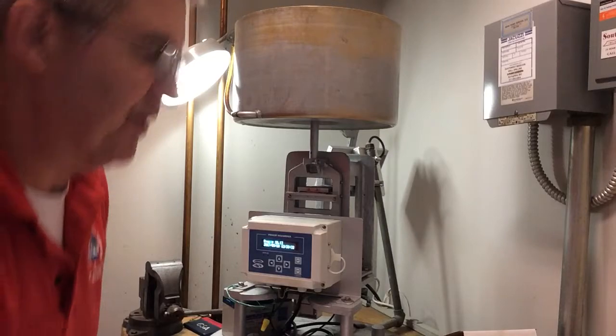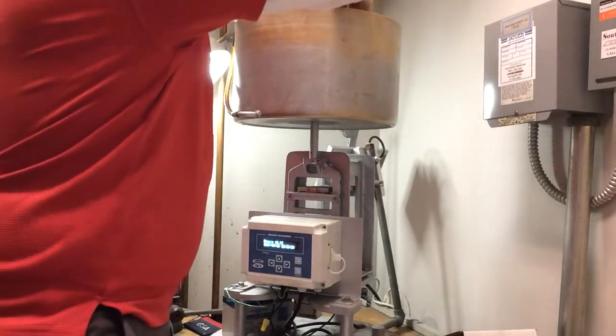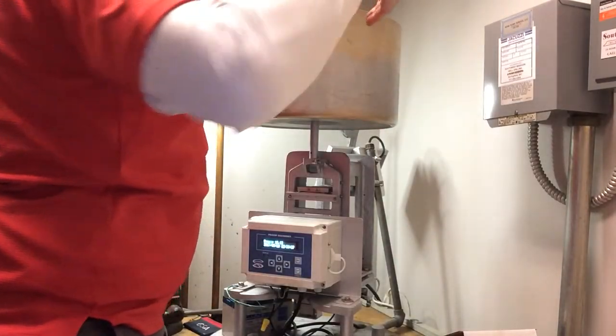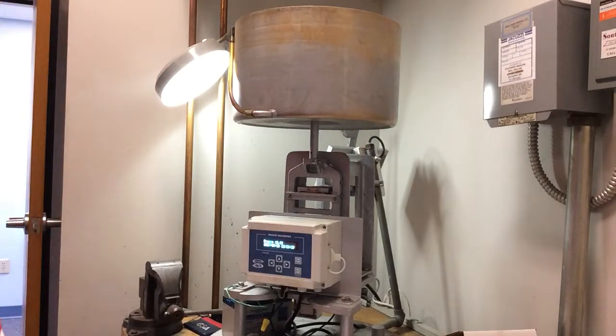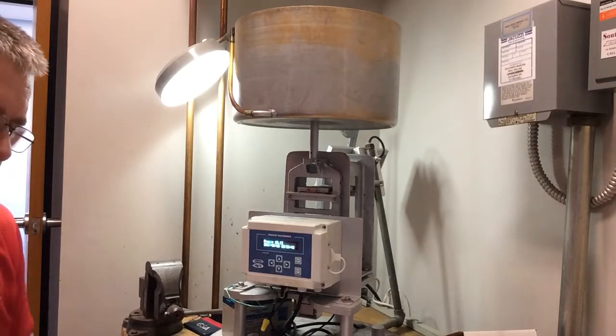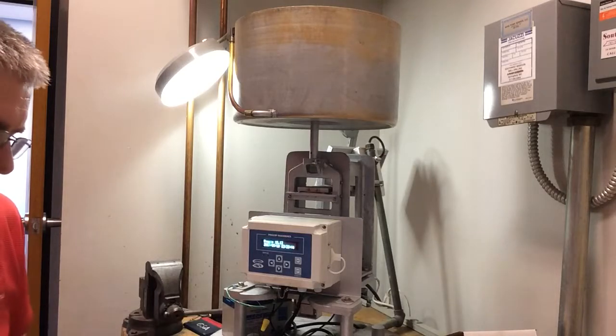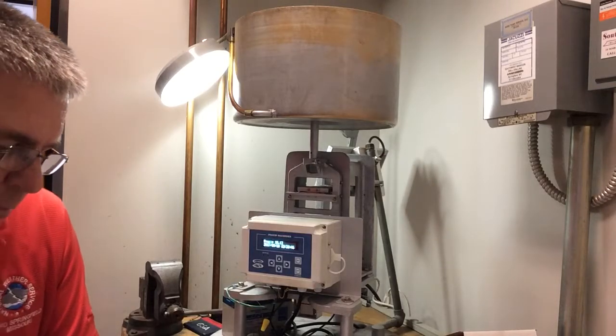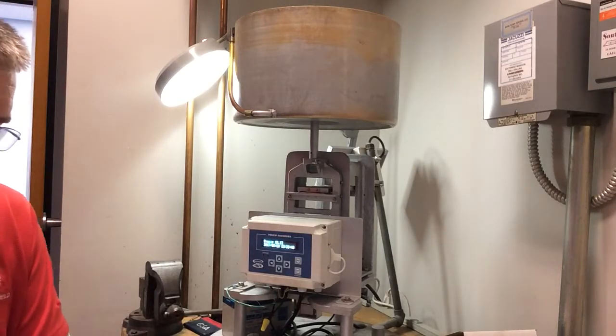Now finally we'll do the third weight. Okay, we'll put that in there. It should read about 15.13 if it's doing well, and it's showing about 15.13. Again, you take that reading, 15.13, and subtract the 0.13 of that empty bucket, and it comes up with 15.